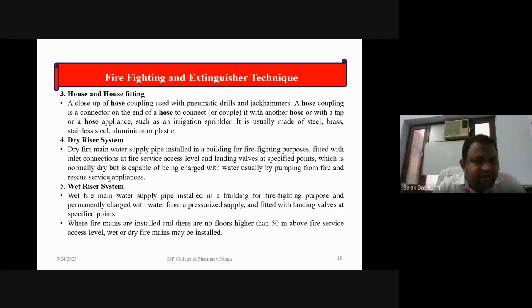Dry riser system. A dry riser is a main water supply pipe installed in the building for the firefighting process, fitted with an inlet connection at fire service access level and landing valves at specified points, which is normally dry but is capable of being charged with water, usually by pumping from fire and rescue service appliances. Wet riser system. A wet riser is a main water supply pipe installed in a building for firefighting purposes and permanently charged with water from a pressurized supply and fitted with landing valves at specified points. Where fire mains are installed, and there are no floors higher than 50 meters above fire service access level. Wet or dry risers may be installed.